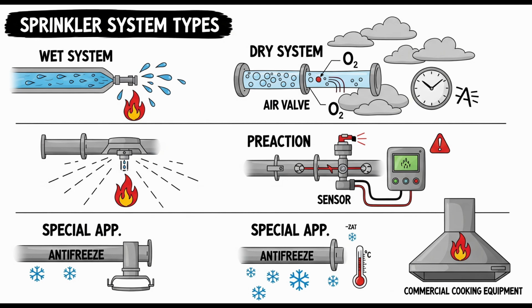For horizontal duct runs, sprinklers or nozzles are required on 10-foot centers, starting no more than 5 feet from the duct entrance. Every 10 feet along the horizontal runs, that provides coverage down the line. Any exceptions for horizontal ducts? Yes, sprinklers or nozzles aren't required in the horizontal ducts if the total length of those horizontal ducts is 75 feet or less and the entire exhaust duct system is protected according to the requirements of NFPA 96. So if you meet the protection requirements of NFPA 96, which covers ventilation control and fire protection for commercial cooking, you might not need sprinklers inside shorter ducts per NFPA 13, interplay between standards again. Yes, NFPA 96 is the primary standard for kitchen exhaust systems.